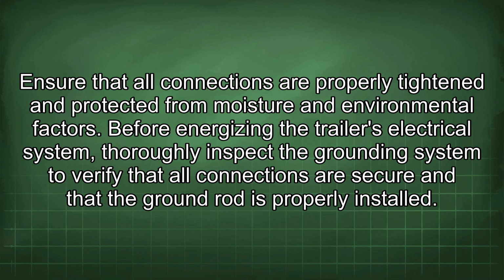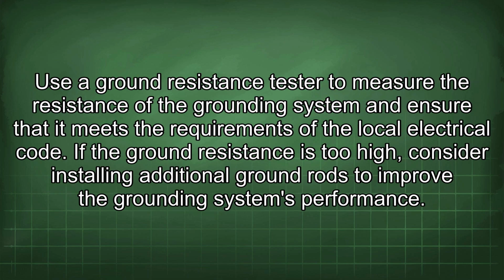Before energizing the trailer's electrical system, thoroughly inspect the grounding system to verify that all connections are secure and that the ground rod is properly installed. Use a ground resistance tester to measure the resistance of the grounding system and ensure that it meets the requirements of local electrical code. If the ground resistance is too high, consider installing additional ground rods to improve the grounding system's performance.